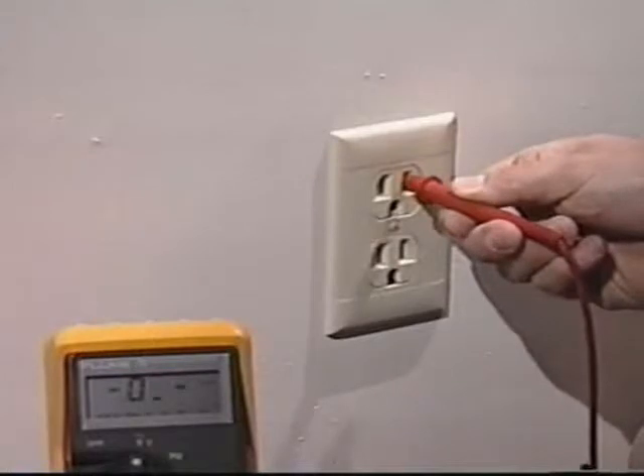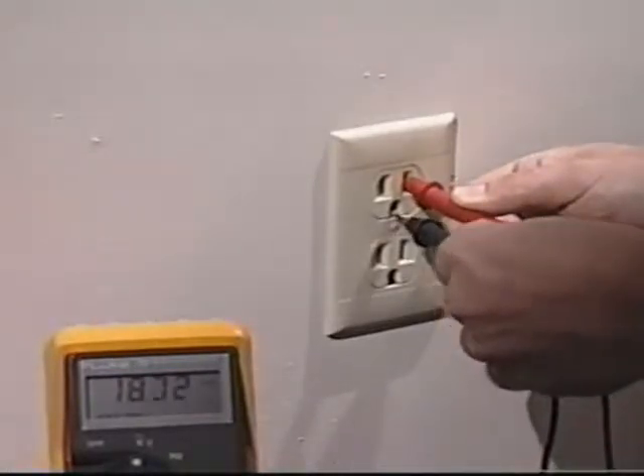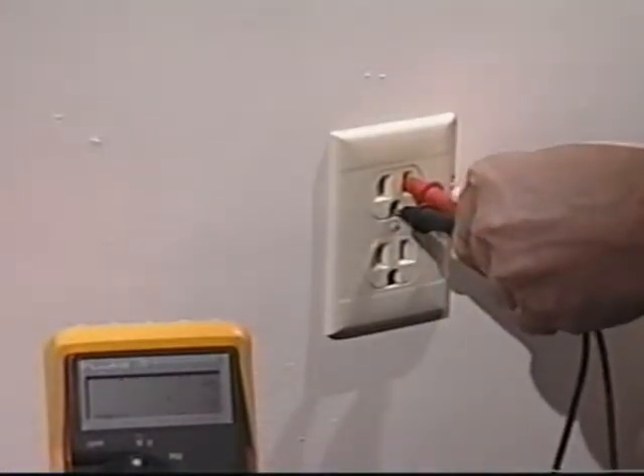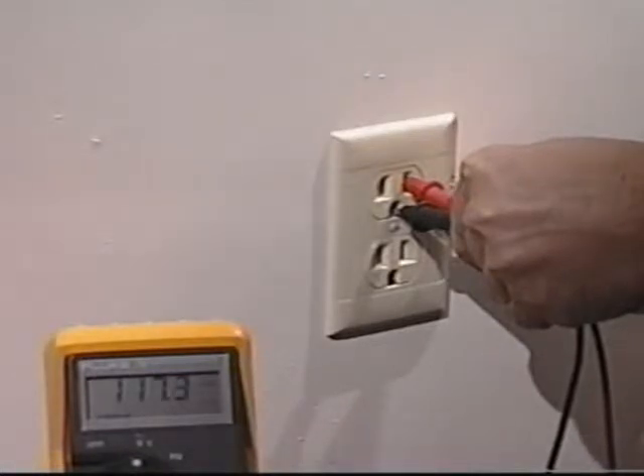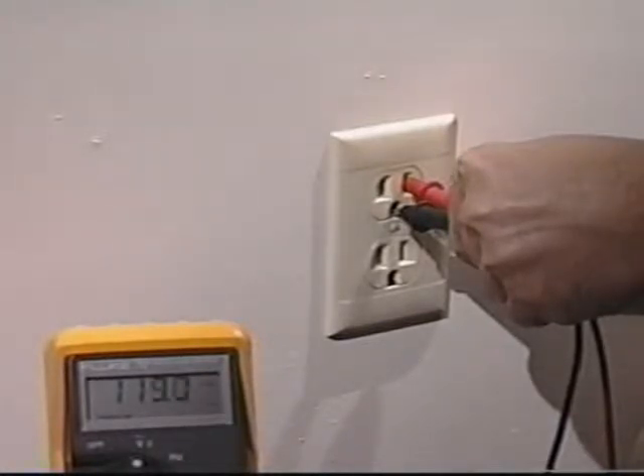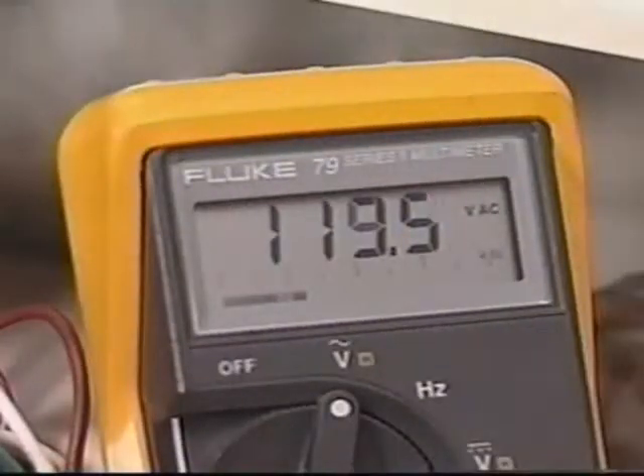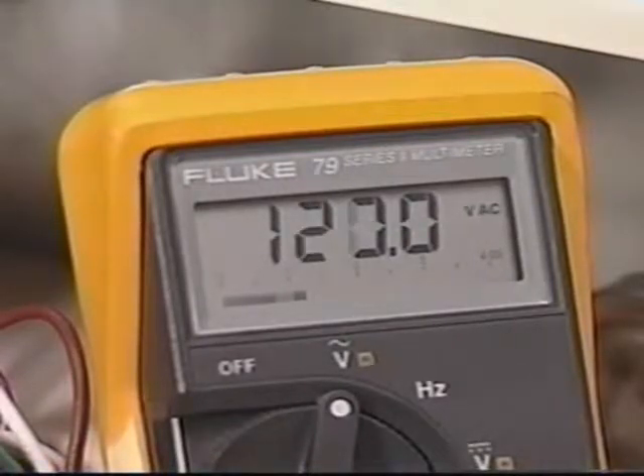Before making any electrical checks, let's test the incoming line voltage at the outlet. Neutral is the large terminal. Line 1 is the small terminal. Ground is the rounded terminal. The polarity check is made to ground. Line 1 should read voltage to ground, indicating proper polarity. Under load, the line voltage should be 120 plus or minus 12 volts AC. For test purposes, we will read voltage to neutral.